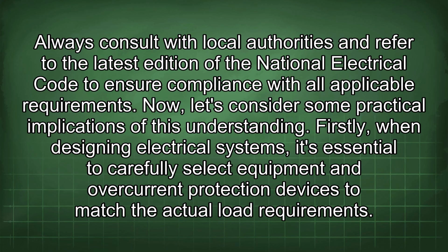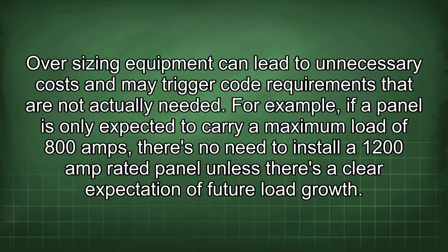Firstly, when designing electrical systems, it's essential to carefully select equipment and overcurrent protection devices to match the actual load requirements. Oversizing equipment can lead to unnecessary costs and may trigger code requirements that are not actually needed. For example, if a panel is only expected to carry a maximum load of 800 amps, there's no need to install a 1200 amp rated panel unless there's a clear expectation of future load growth.